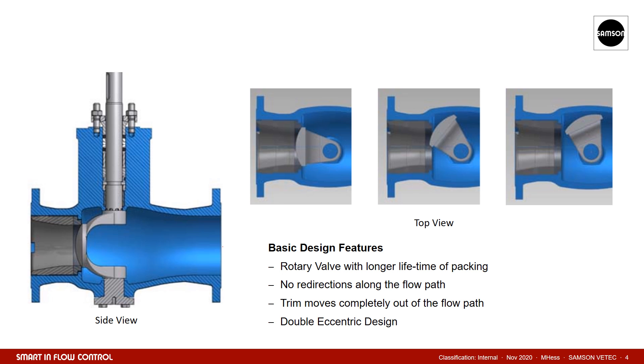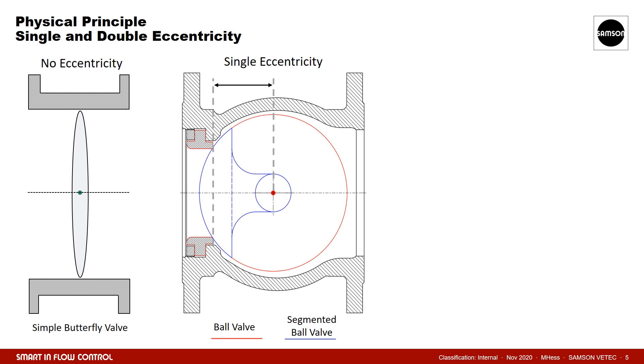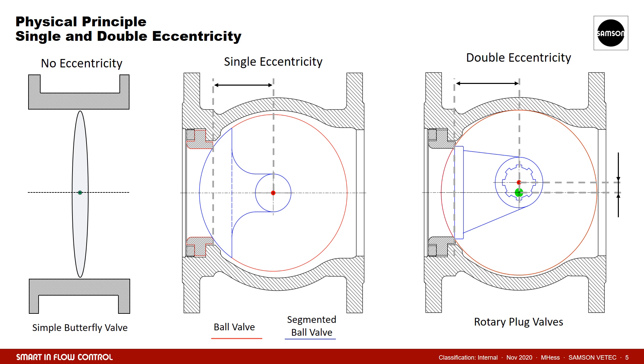Rotary plug valves by definition have a double eccentric design. A design without any eccentricity is represented by the classic low-cost butterfly valve shown on the left, where the rotation axis is right inside the middle of the plate. The image in the middle shows a single eccentric design, representing a ball or segmented ball valve, where the axis of the sealing edge is not aligned to the rotation axis. In the right image, there is an additional eccentricity — the rotation axis, marked by the red point, moves slightly out of the middle of the flow axis, highlighted in green.